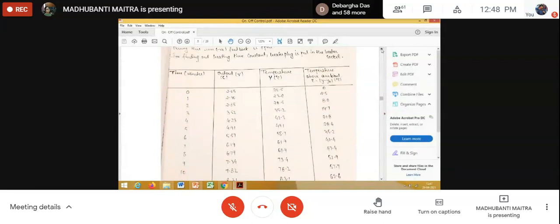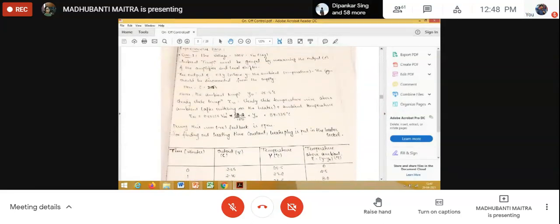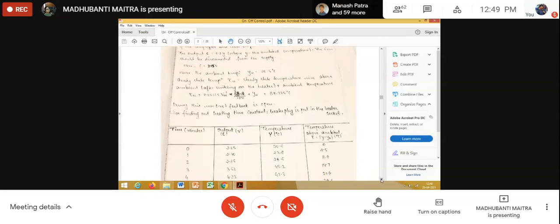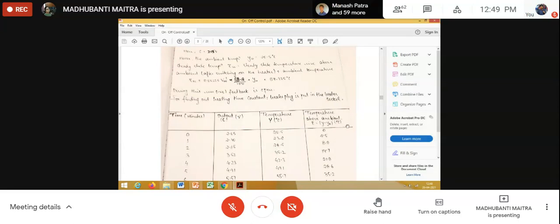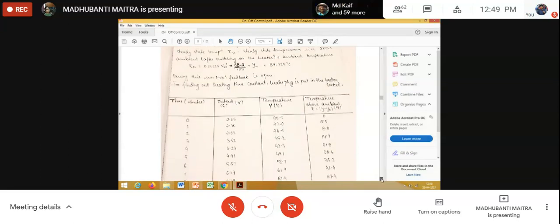So here you can see that this is the value of C, and from that value of C we have calculated the ambient temperature as 20.5 degrees centigrade. Now, using this value and taking 63.2% of that, for calculating the time constant, we have calculated the temperature rise above ambient. That means we'll have to raise the temperature of the plant at least up to this value, otherwise we'll not be able to calculate the heating time constant.